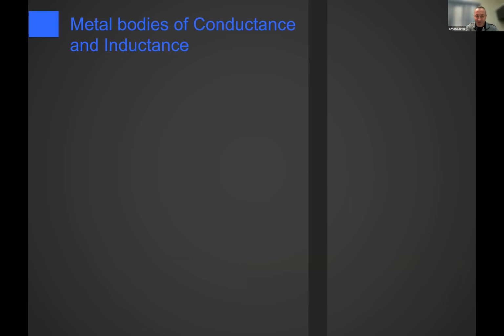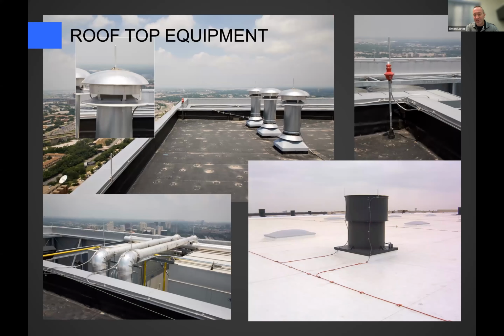I will briefly explain what a metal body of conductance is. A metal body of conductance is an item on a roof that sticks up outside the zone of protection and requires lightning rods or a connection to the lightning protection system because it is subject to a direct strike. That is a metal body of conductance.